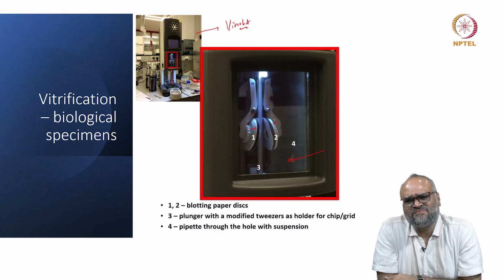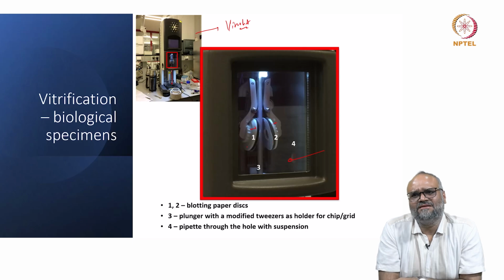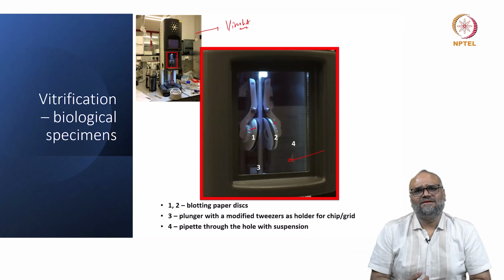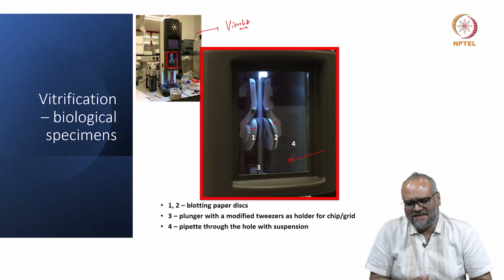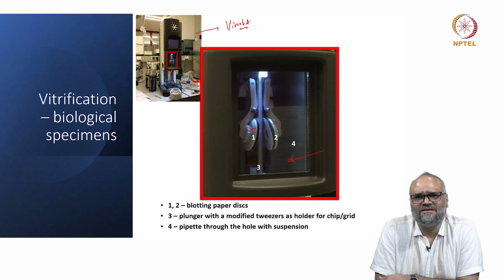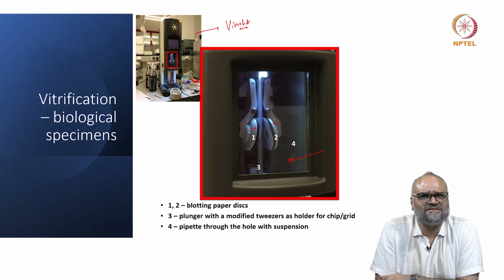Before preparing specimens, you typically do something called glow discharge of the carbon grid, so that you make the grids really hydrophilic, and when I drop a liquid on it, it spreads in a large area. All these methods that I have spoken to you about till now involve a great amount of patience, skill, and experience matters. If you've had any of your group mates who have prepared similar kinds of systems before, please discuss with them which scenarios do not give you a very good sample. So once you prepare these kinds of specimens, you can take them to the microscope and start imaging.